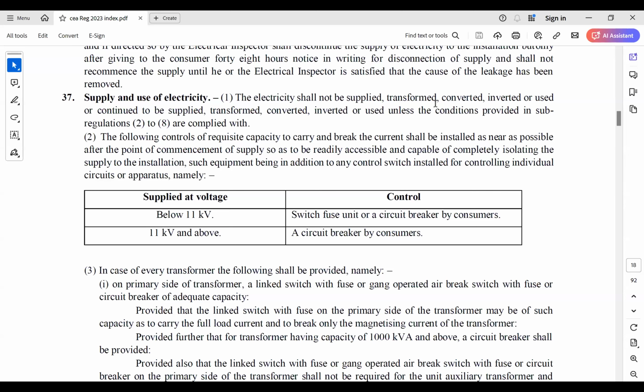But what happens is, we provided the UG cable to the DISCOM to connect to their overhead 11 kV line. Now, technically, if the DISCOM wanted to make a good electrical installation, they have to have a two-pole structure on that particular part and they have to take the supply properly. Instead, they told us they don't have money for putting a two-pole structure there, or maybe a structure outside. What they did is they took the cable through the post, tied the cable to the post, and at the top they did something like a hookup. The UG cable is hooked to the line.